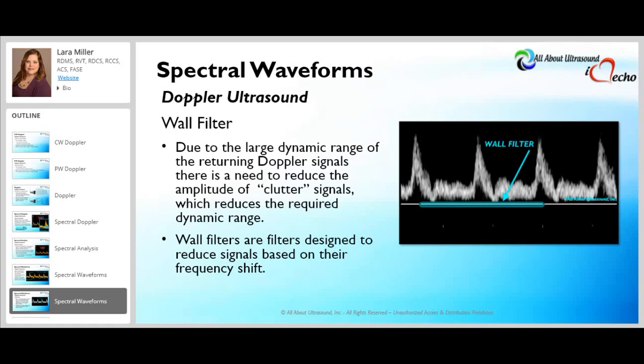A wall filter is used to clean up the Doppler signal and spectral display. Doppler signals have a large dynamic range that can include low-level amplitude clutter signals. The wall filter reduces signals based on their frequency shift, attenuating those low-frequency signals near the baseline — the so-called wall thump — which come from tissue and artifactual motion rather than true blood cell frequency shifts. Wall filters act as high-pass filters, passing signals with frequency shifts above the wall filter threshold and attenuating those below it.